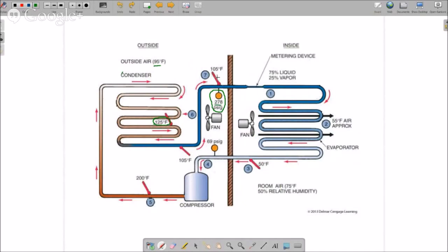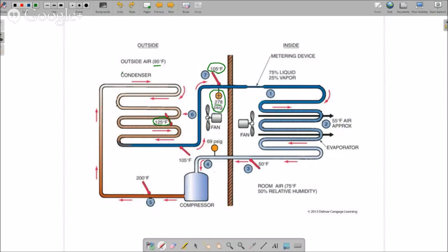Yet you have your thermometer right here where your gauge is connected to the liquid line and it's reading 105 degrees. That gets confusing for some new technicians. What you have to think about is when you hook your gauge up to the liquid line or the high side, you need to picture in your mind that you are measuring the temperature at the exact center of the condensing coil.